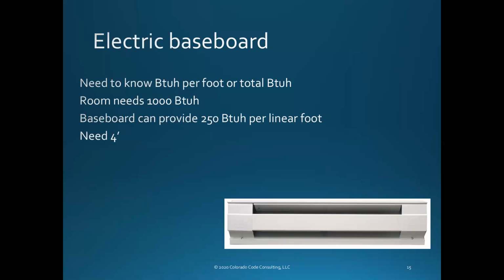In this particular case, electric baseboard, right? The codes say that you can't use it? No, it doesn't say that at all. So electric baseboard's not too difficult, particularly. I need to know my BTU per foot or the total BTU for a particular electric baseboard heater. If I need 1,000 BTUs in that room, and it's got 250 BTUs per linear foot, I need a 4-foot baseboard in that room. Not hard. Those are easy. You just don't see that very often.